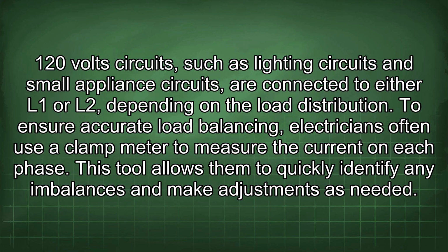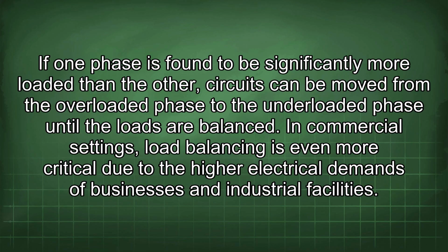120-volt circuits, such as lighting circuits and small appliance circuits, are connected to either L1 or L2, depending on the load distribution. To ensure accurate load balancing, electricians often use a clamp meter to measure the current on each phase. This tool allows them to quickly identify any imbalances and make adjustments as needed. If one phase is found to be significantly more loaded than the other, circuits can be moved from the overloaded phase to the underloaded phase until the loads are balanced.